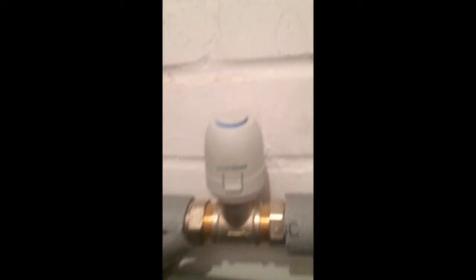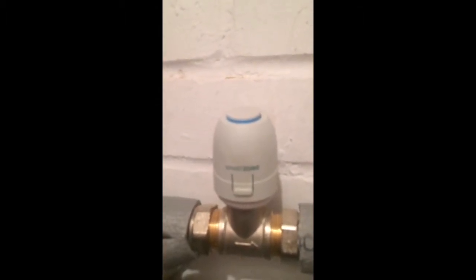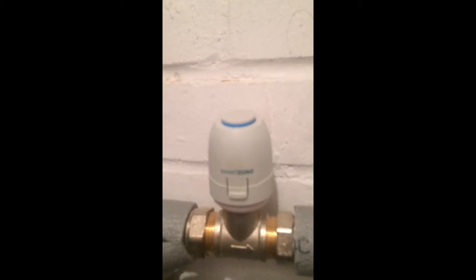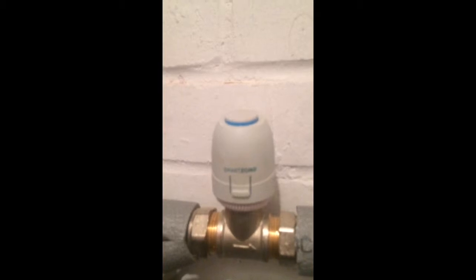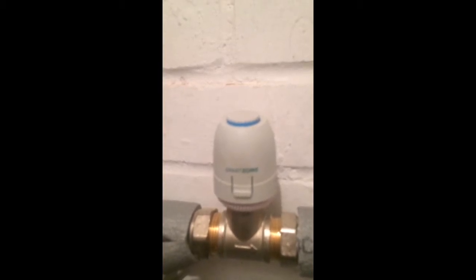So these are the new smart zone valves from Guardian — just clip on, clip off, like that, very simple. Basically you can see we've got a call for heating and it slowly makes its way fully open, so it doesn't open and close instantly. It actually takes time, giving itself a slight buffer, which is supposed to reduce noise — which I can imagine it does.